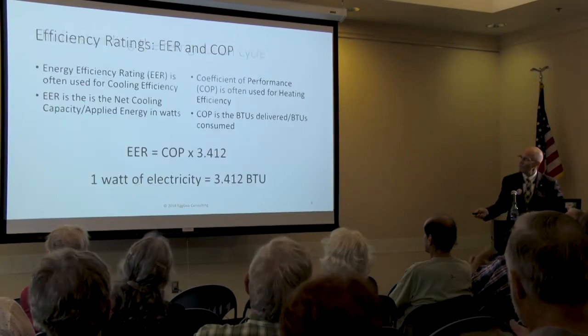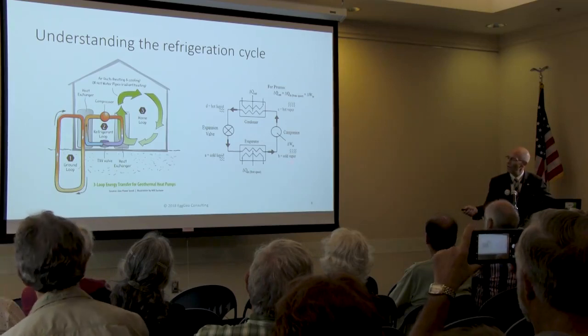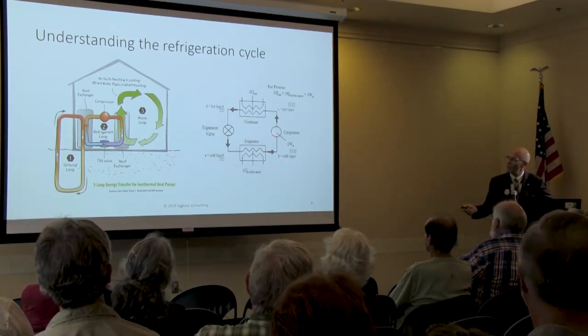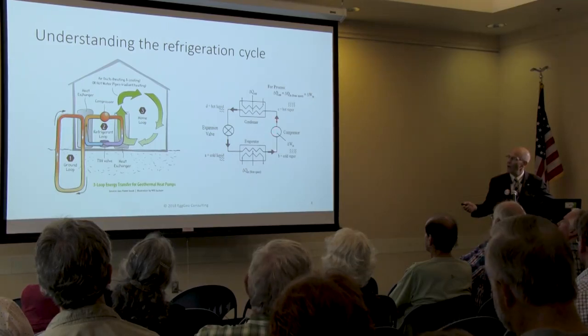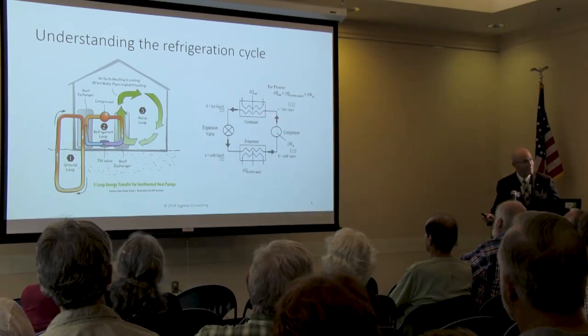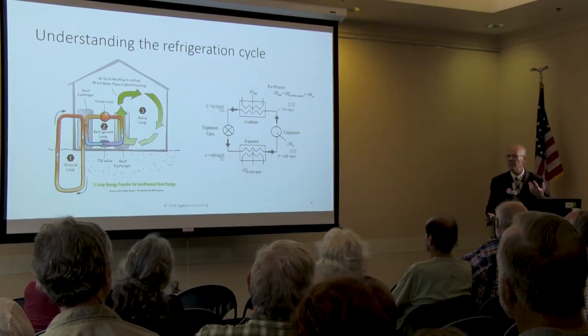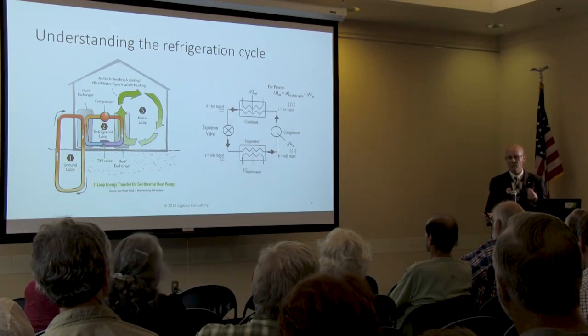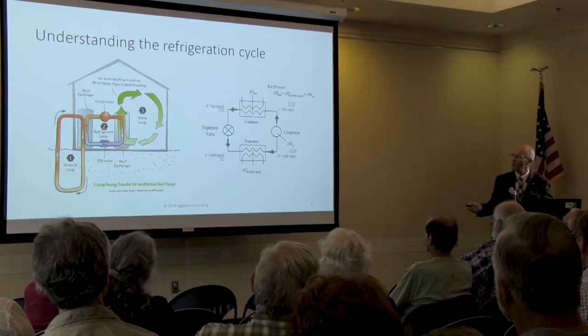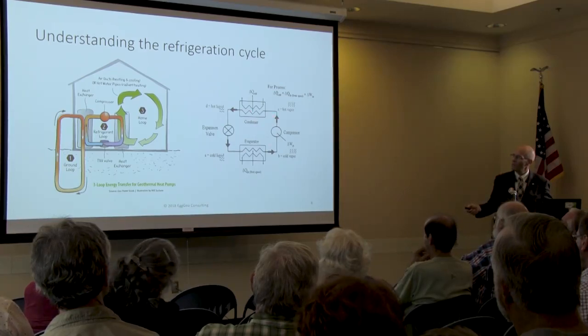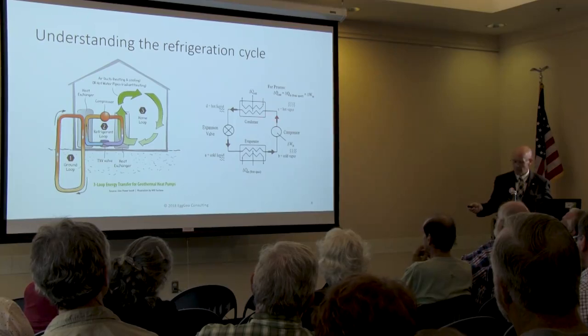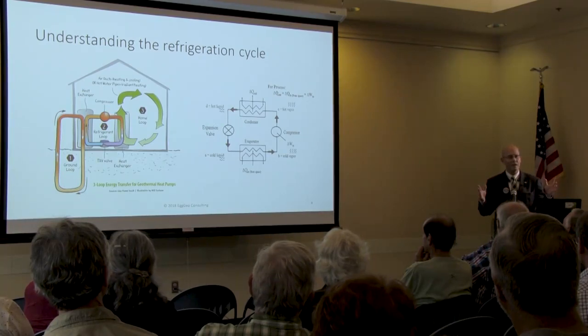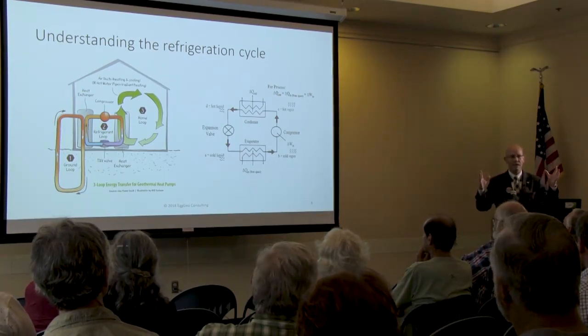The reason for these particular parts, I'm going to go back because I abbreviated this, sometimes I have a better explanation, is the compressor actually compresses a cool vapor to a hot, high-pressure vapor, and that's how it manipulates the available heat in any system. One of the questions we will get constantly is, if it's 50 degrees in the ground, how do we get that to a comfortable temperature in the middle of the winter? It's through the Carnot refrigeration cycle, and this compressor is the key to that. It compresses a low temperature, low pressure vapor to a high temperature, high pressure vapor. And I'm just going to say it like this. When you're dealing with any vapor, any gas, the amount of energy in a cubic foot, for example, if it's compressed to 1/10 the size, the same energy is still going to be in there, but that is manifest by a higher temperature.